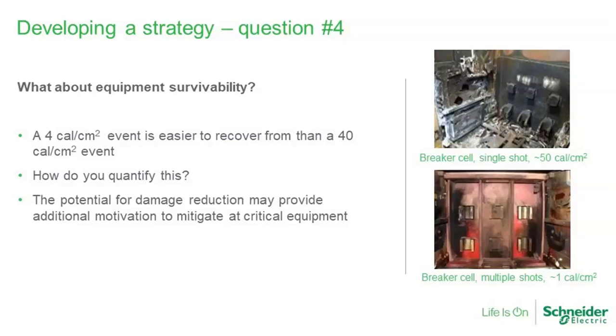And this may be one of the considerations. We've had discussions with some folks that are operating critical facilities, data centers, hospitals, where this has been part of the consideration in bringing incident energy levels down at certain equipment. I would just say, certainly it's not a bad idea, because nobody wants equipment damage, right? But you have to be a little bit careful about applying this as one of your criteria. If you stick to this strictly, then you might wind up throwing out certain things like arc flash maintenance switches that are only active part of the time, so you really may not be able to count on them all the time to help reduce equipment damage. But for personnel safety, they may be perfectly wonderful solutions that you can apply. Certainly, equipment survivability is something to think about, but it may not be the thing that you can use to drive the bus, so to speak, in all cases, because it moves your solutions in a certain way.